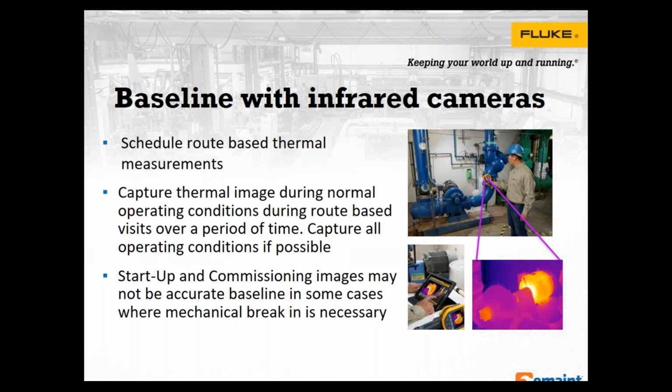It's good to get out there initially, when you set up the workflow or the procedure on how to do it. I can't tell you how many times we've seen the thermal camera in the hands of different operators who maybe don't have any thermography training. It doesn't necessarily have to have the training. It's good to have a base level of training, but if the camera's set up properly and the stand is marked, it's really a focus-and-shoot type of situation. But these are things to consider as far as being consistent and the quality of data coming in.